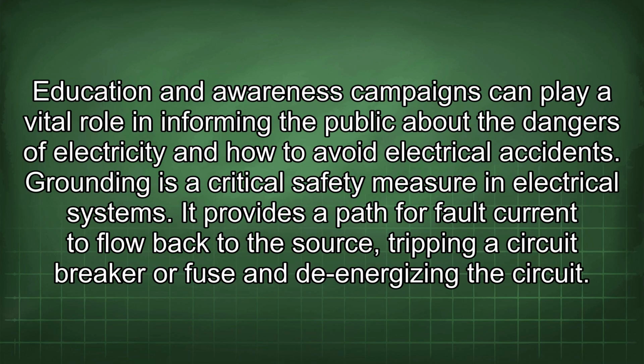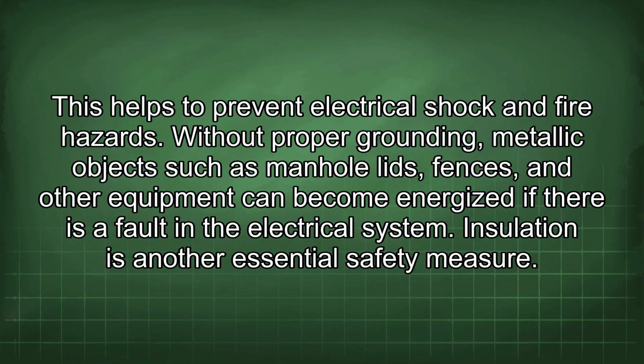Education and awareness campaigns can play a vital role in informing the public about the dangers of electricity and how to avoid electrical accidents. Grounding is a critical safety measure in electrical systems. It provides a path for fault current to flow back to the source, tripping a circuit breaker or fuse and de-energizing the circuit. This helps to prevent electrical shock and fire hazards. Without proper grounding, metallic objects such as manhole lids, fences, and other equipment can become energized if there is a fault in the electrical system.